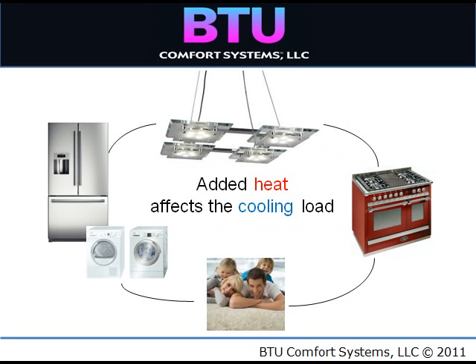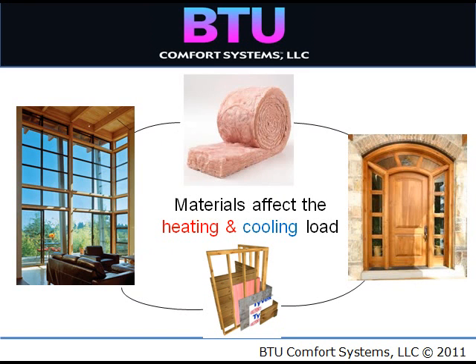Lighting is one of the major contributors to heat gain within a structure. Kitchen cooking appliances, people, laundry equipment, and refrigerators are additional factors that need to be taken into account when designing a system. Materials selected before a structure is built have lasting effects on the mechanical system requirements well into the future. Wall types, 2x4s, 2x6s, SIPs, ICFs, and a host of other choices can dramatically change the heating and cooling loads of a structure. Windows are a major source of heat transfer.